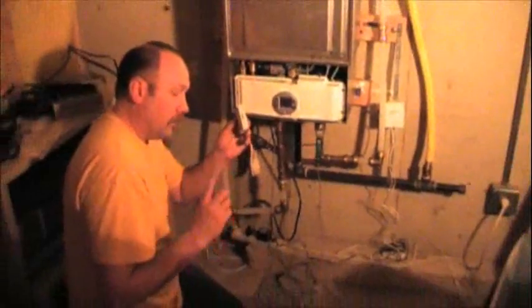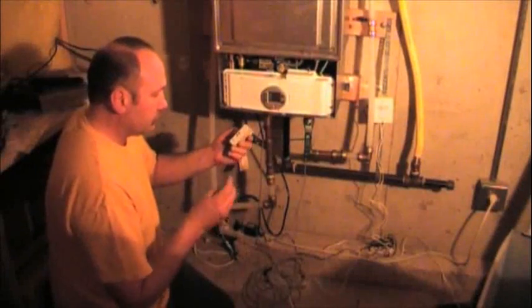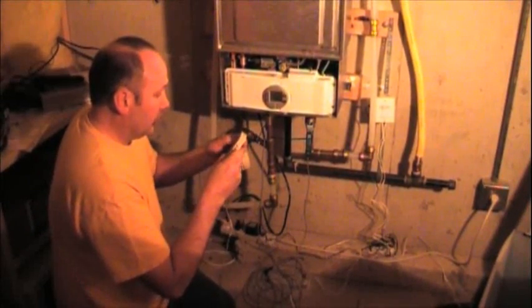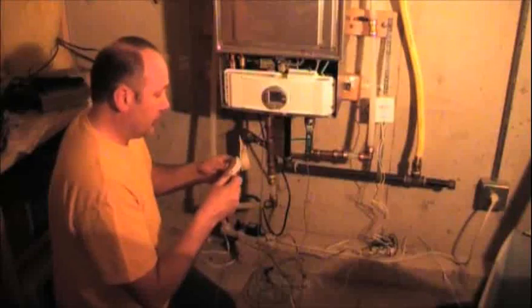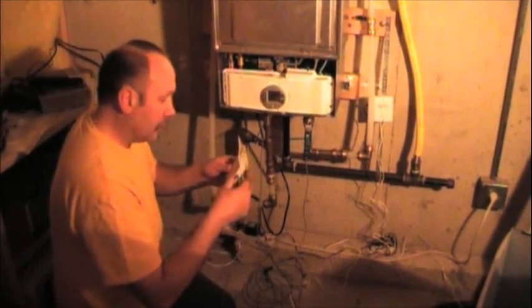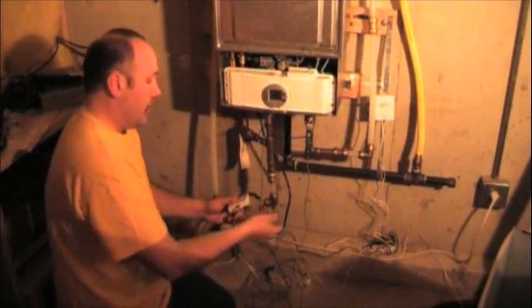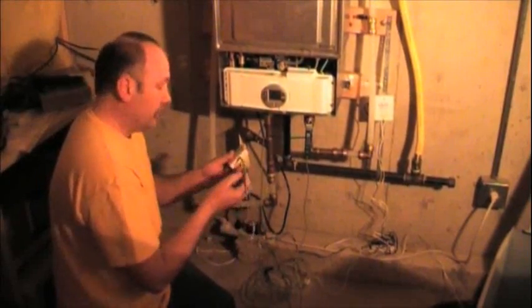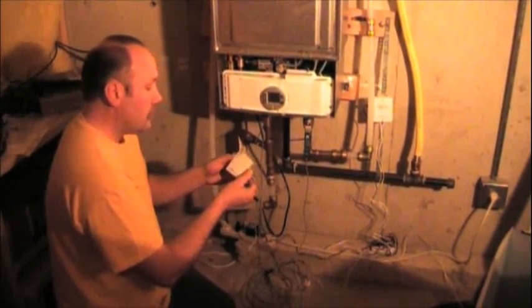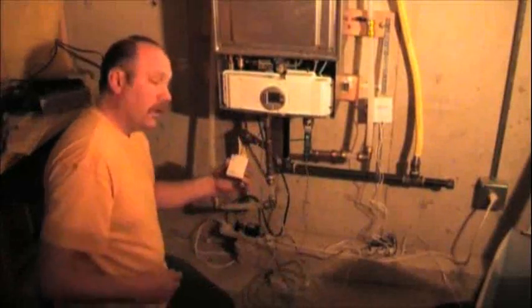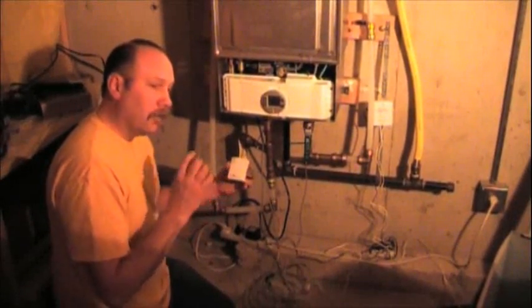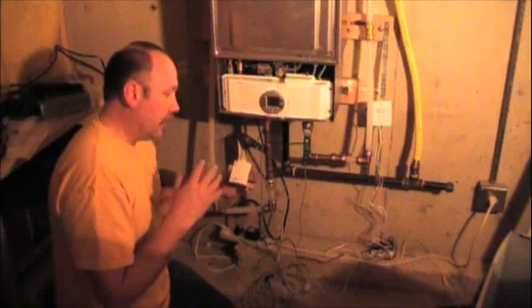Now, we then plug those two other ends into the HOBO data logger. I'm going to plug the cold into the top, which would be channel 3, and the hot coming out into the bottom, which would be channel 4. Then, one of the things you want to do is not handle the data logger once you have pushed the button, because you can affect it by rattling the wires a little bit. So I'm going to set it on the floor, then I'm going to push the button.